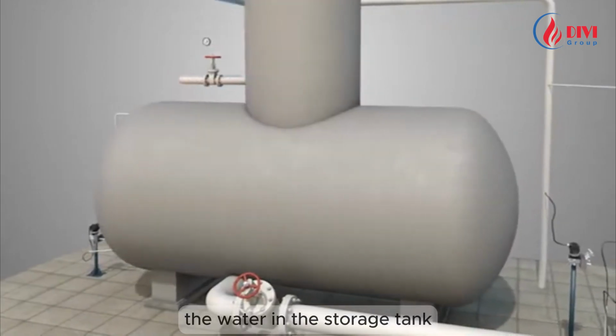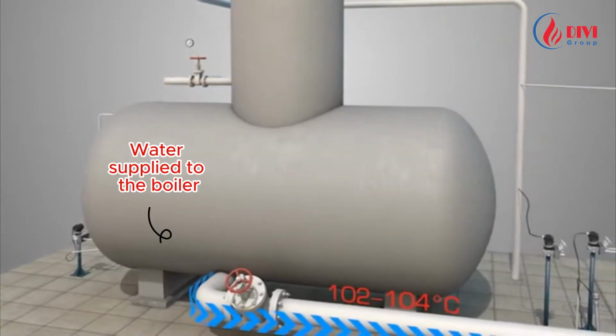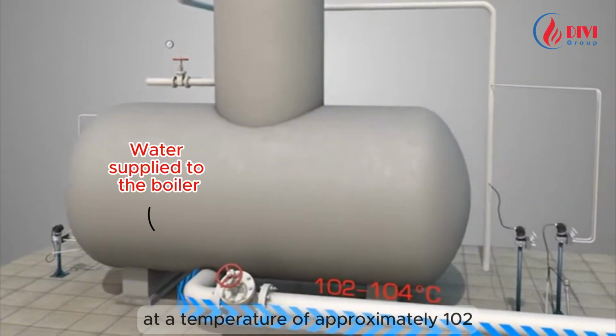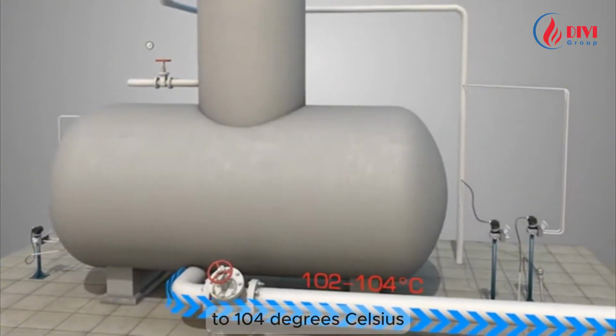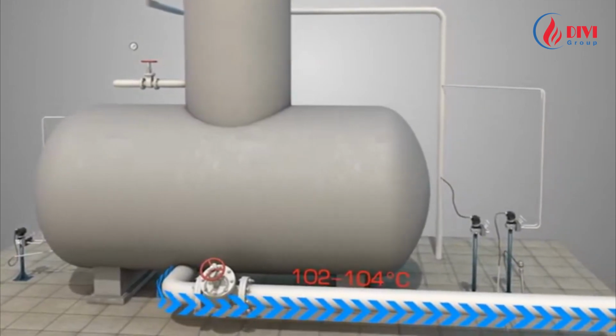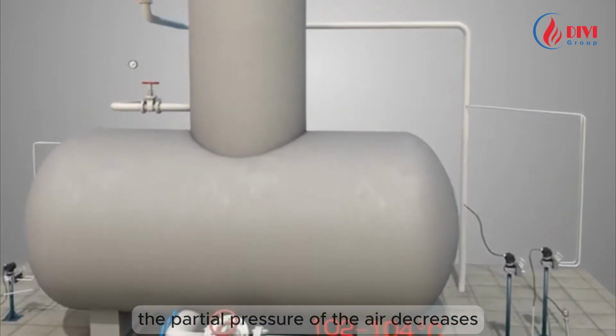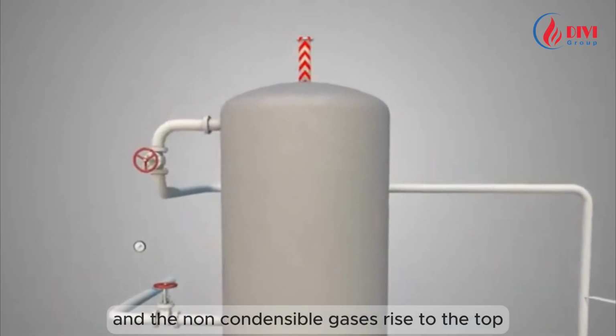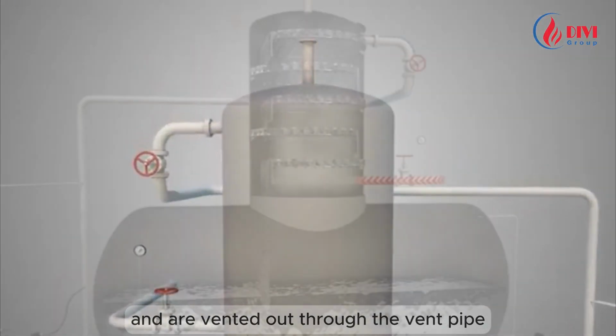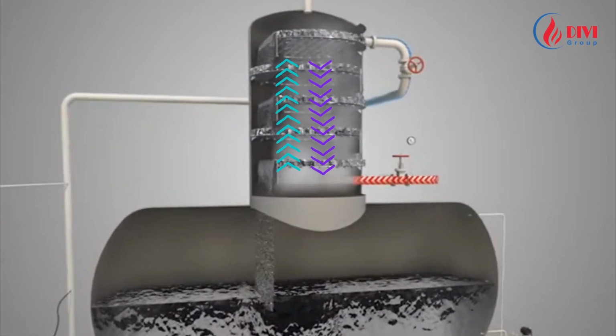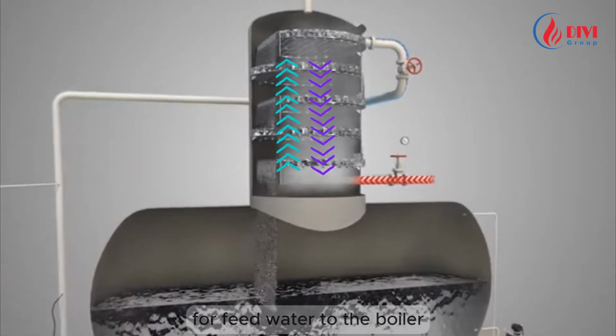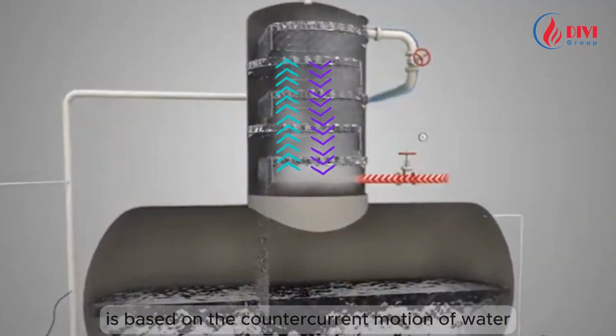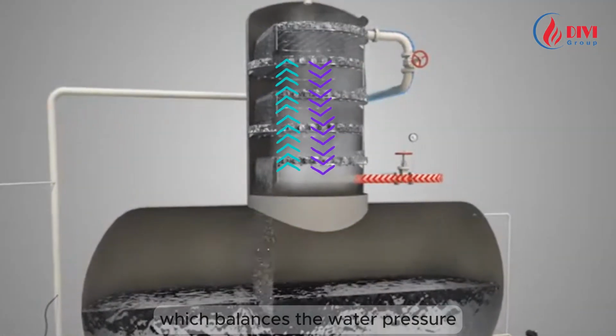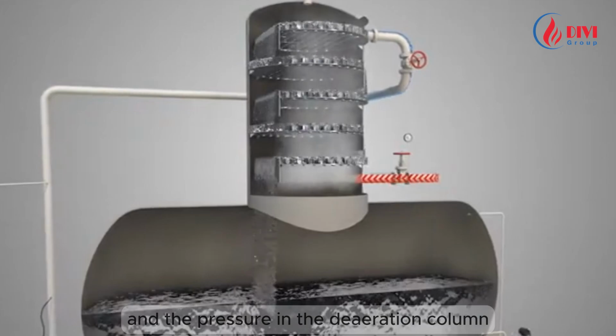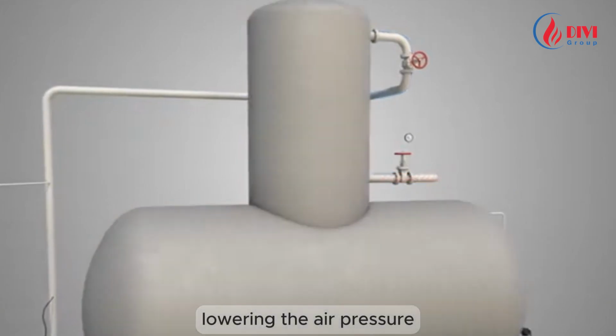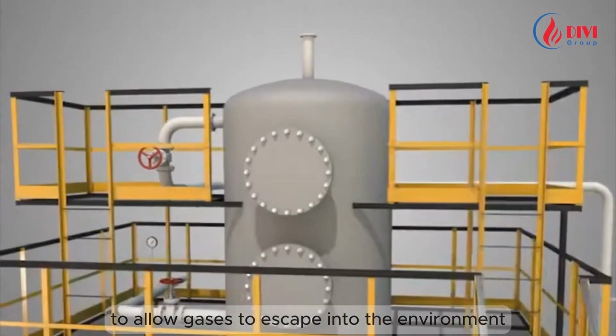The water in the storage tank, after deaeration, is fed into the boiler at a temperature of approximately 102 to 104 degrees Celsius. Meanwhile, the partial pressure of the air decreases, and the non-condensable gases rise to the top and are vented out through the vent pipe. In other words, the operating principle of the Deaerator for feed water to the boiler is based on the countercurrent motion of water and steam, which balances the water pressure and the pressure in the deaeration column, lowering the air pressure to allow gases to escape into the environment.